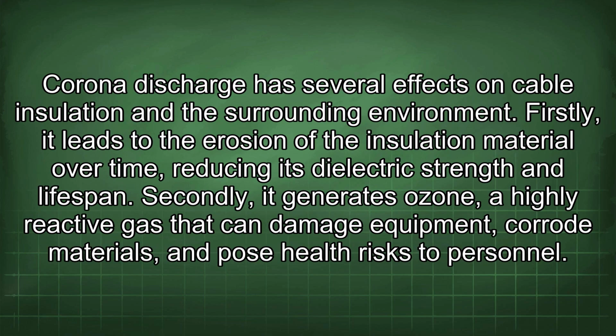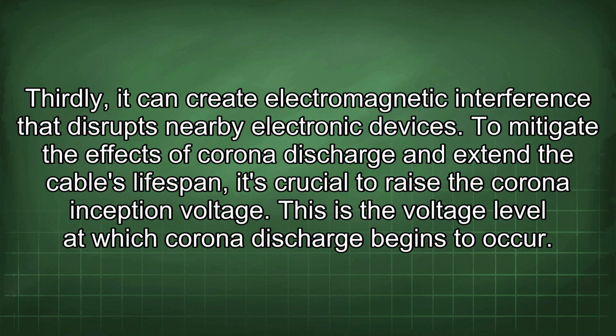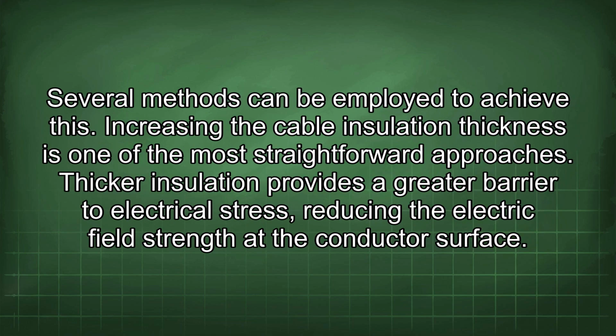Corona discharge has several effects on cable insulation and the surrounding environment. Firstly, it leads to the erosion of the insulation material over time, reducing its dielectric strength and lifespan. Secondly, it generates ozone, a highly reactive gas that can damage equipment, corrode materials, and pose health risks to personnel. Thirdly, it can create electromagnetic interference that disrupts nearby electronic devices. To mitigate the effects of corona discharge and extend the cable's lifespan, it's crucial to raise the corona inception voltage. This is the voltage level at which corona discharge begins to occur. Several methods can be employed to achieve this.